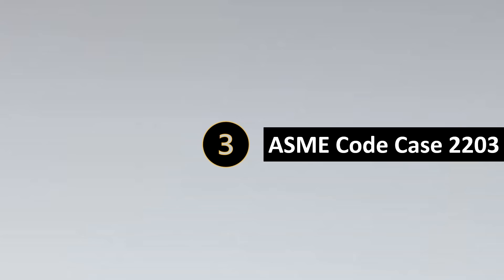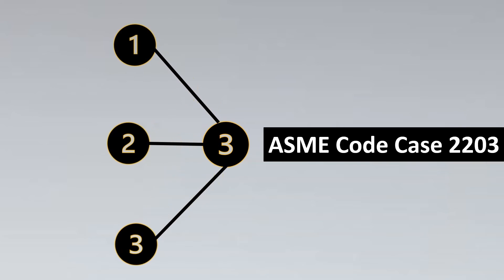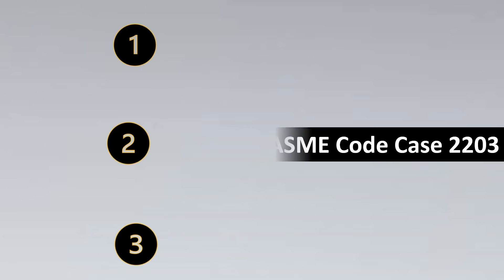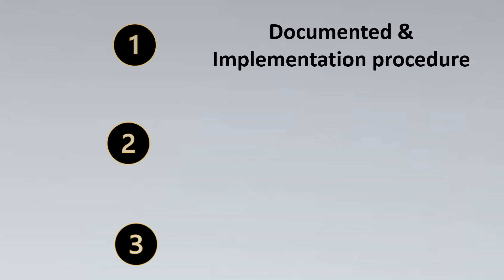The most important question of all: what is ASME code case 2203? This code case 2203 is specially used when you don't want to use a lever in such cases. It has a 3-step procedure that we need to follow. The first condition is that a documented procedure for testing of the relief valve should be done. Since the basic purpose of a relief valve lever is to do periodic testing, if you are not using a lever, you must have a strong documented procedure for how you are going to check the relief valve — and it should be an implemented procedure, not just a document.